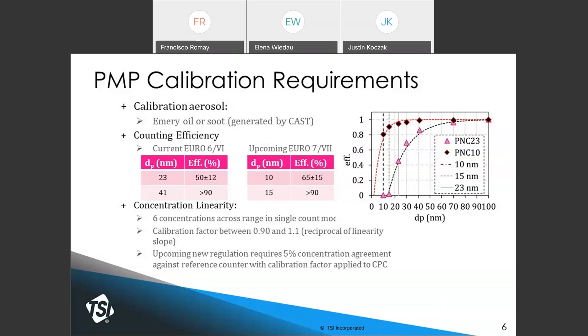CPCs can be calibrated with either emery oil or soot generated by a CAST or mini-CAST. At TSI, we use emery oil. Typical counting efficiency curves show that for the new 10-nanometer CPCs, the efficiency curve is sharper, due to the way CPCs work — you get a sharper response with respect to size when going to lower cut points. At 23 nanometers, the smaller delta-T between condenser and saturator leads to a less steep efficiency curve.